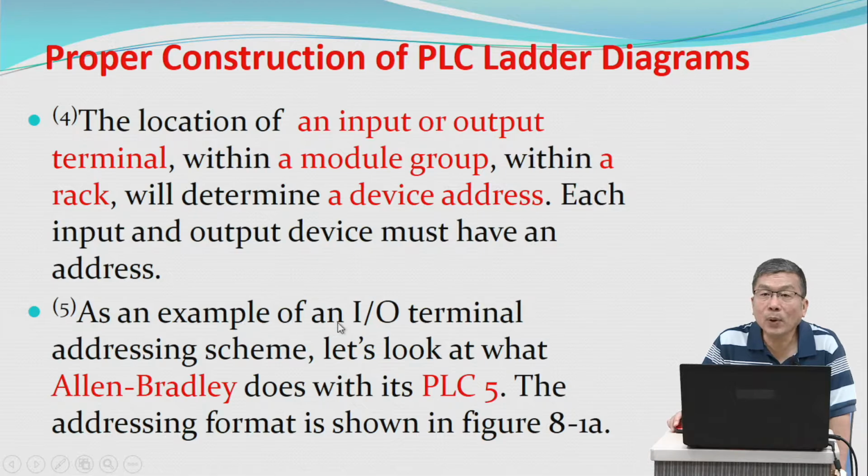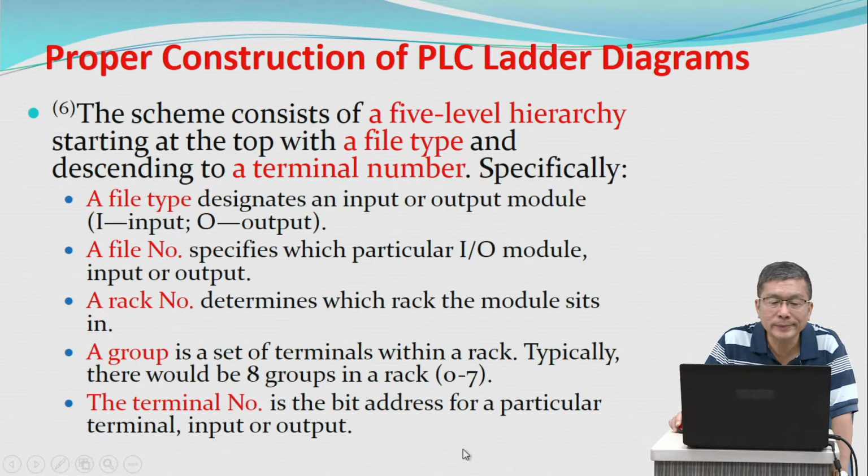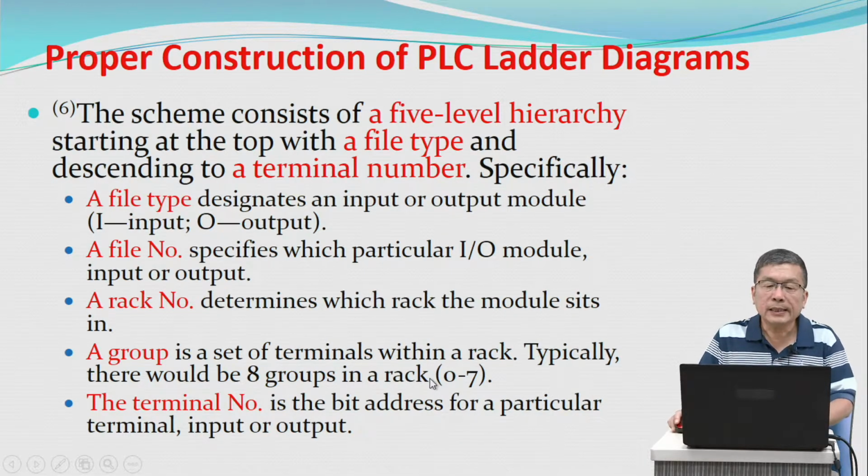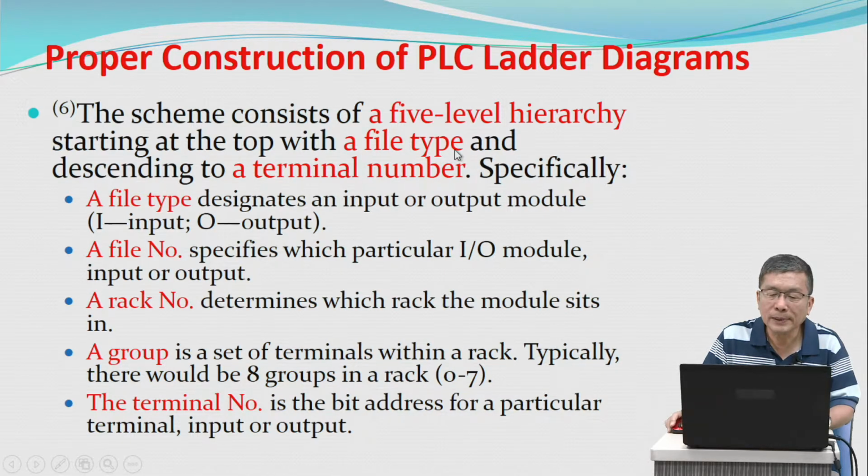As an example of an I/O terminal addressing scheme, let's look at what Allen-Bradley does with its PLC 5. The addressing format is shown in Figure 8.1a. The scheme consists of a five-level hierarchy starting at the top with a file type and descending to terminal number.